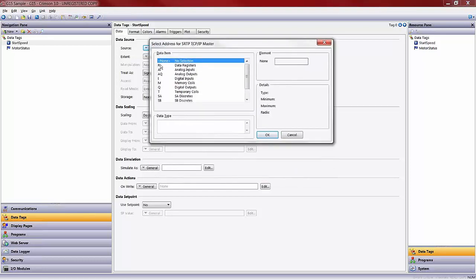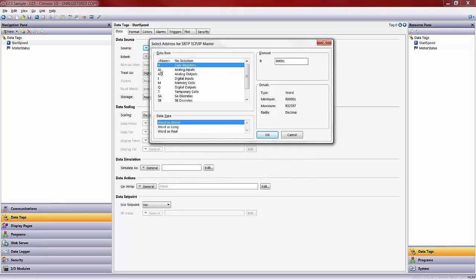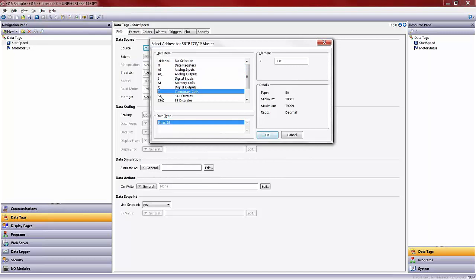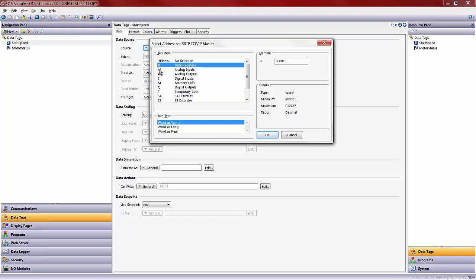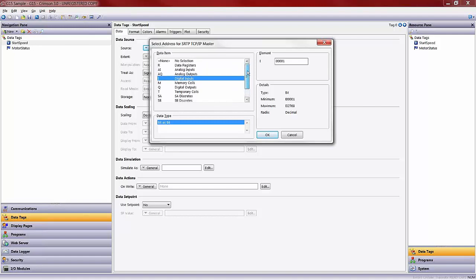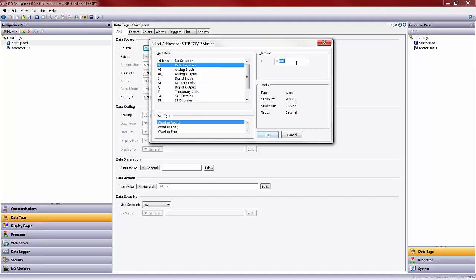I click on GE IP controller, and again, as long as you are familiar with GE IP controllers, you will notice that the addressing here should look the same as what you would see in a GE IP controller of any sort. Percent R, percent AI, percent AQ, percent I, and so on. The percent sign is left off because of redundancy purposes. In this case, I'm going to map this start speed to a percent R, 56, let's say.